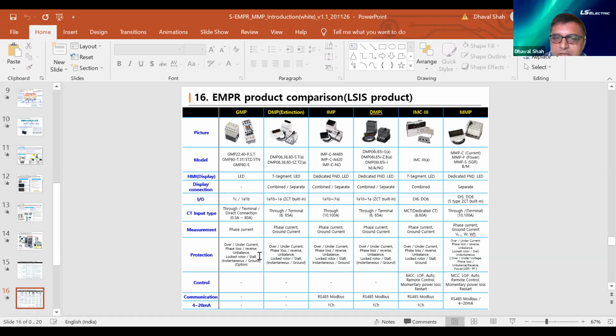So similarly, we see protection: overcurrent, undercurrent, phase loss, reverse, unbalanced, lock rotor. All these basic functionalities of all current related products would be available in GMP. So even if it is the most economical product, you get the highest number of protections in this product. But when you go to the highest level, you also get voltage-based protections, power-based protections, and in 2 units, you also get insulation resistance, whereas you can add what we say the thermistors to the relay.